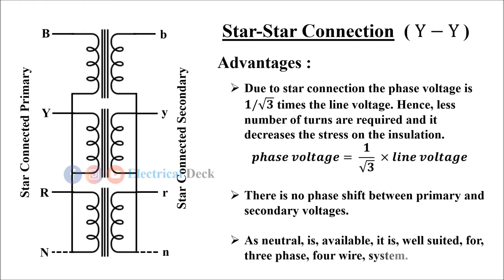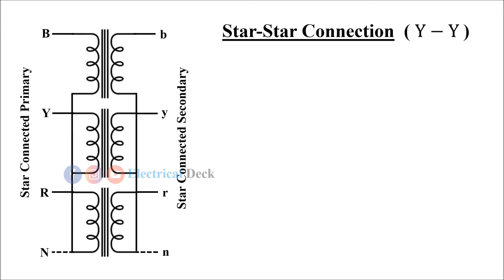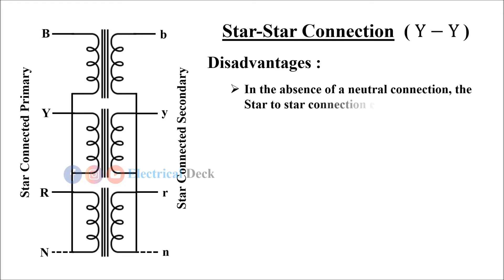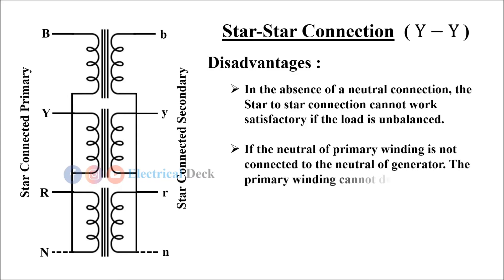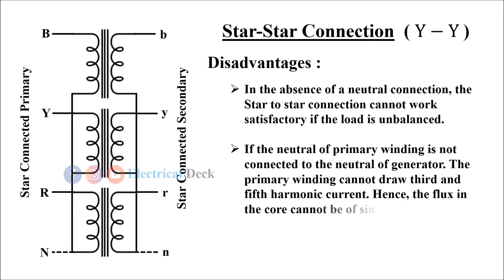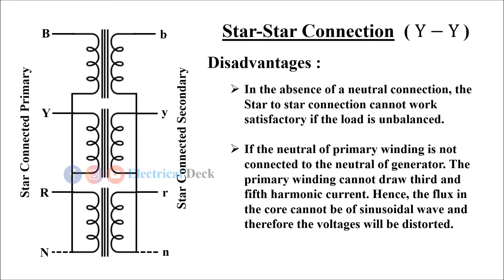But the disadvantages with this type of connection are: in the absence of a neutral connection, the star-to-star connection cannot work satisfactorily if the load is unbalanced. If the neutral of the primary winding is not connected to the neutral of the generator, the primary winding cannot draw third and fifth harmonic current, hence the flux in the core cannot be of sinusoidal wave and therefore the voltages will be distorted.